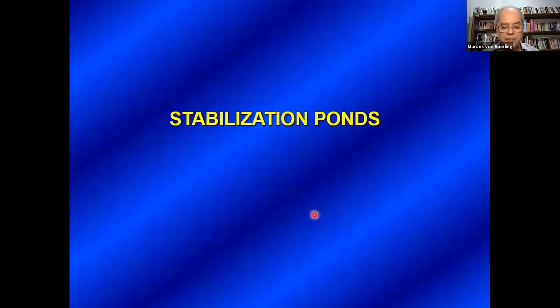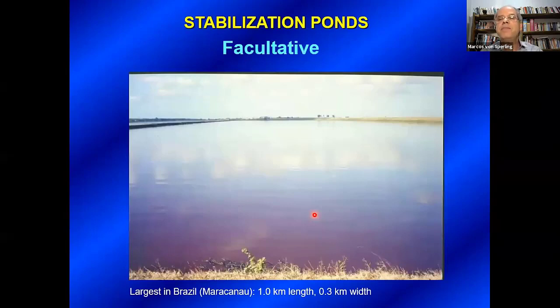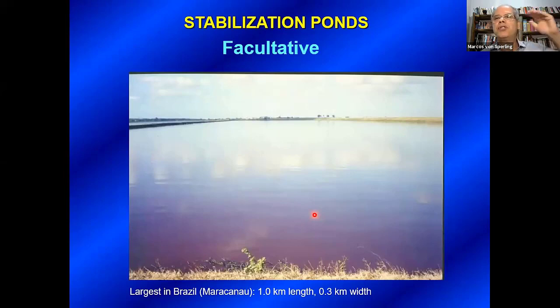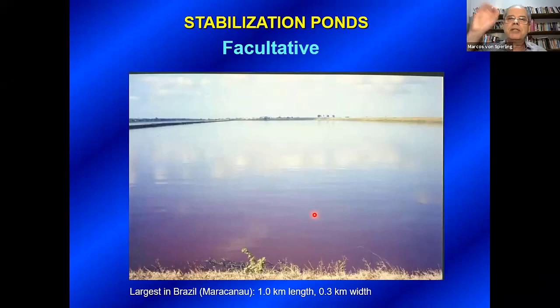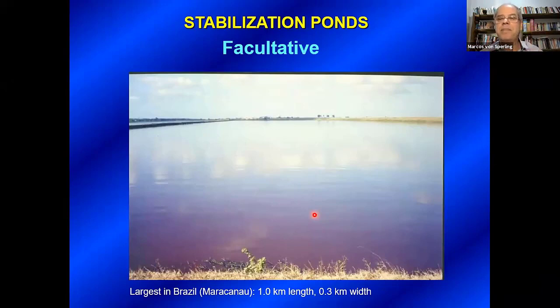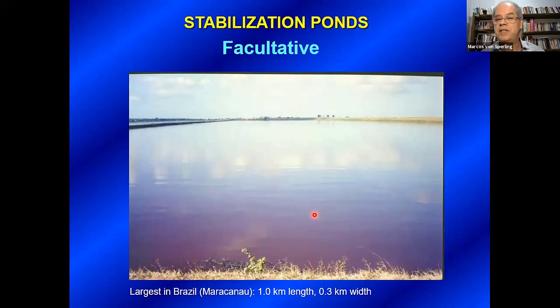Facultative ponds are the most widely used variant, not only in Brazil but in many, many countries. In the United States, there is a fantastic map showing 8,000 stabilization ponds spread all around the country from east to west, from south to north — so regardless of climatic conditions, they are being used. In Australia, they are the dominant treatment process. In France, there are more than 3,000 stabilization ponds. They are a very simple treatment process, limited in their capacity for removing organic matter, but able to remove many pathogenic organisms. The major problem is the large land requirements.